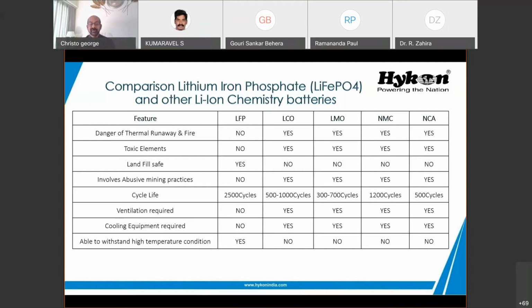Some batteries require ventilation, some don't. The reason is that for LFP, the temperature rise when discharging very high current is less, because the internal resistance is less for LFP. Cooling is not critical for LFP, but all other lithium batteries need cooling, or you cannot discharge very high current. So cooling equipment and requirements are needed for batteries other than LFP.